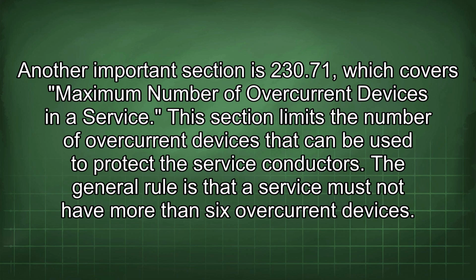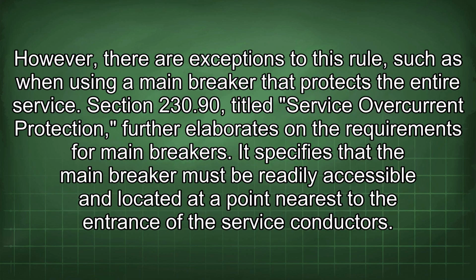Another important section is 230.71, which covers the maximum number of overcurrent devices in a service. This section limits the number of overcurrent devices that can be used to protect the service conductors. The general rule is that a service must not have more than 6 overcurrent devices. However, there are exceptions to this rule, such as when using a main breaker that protects the entire service.